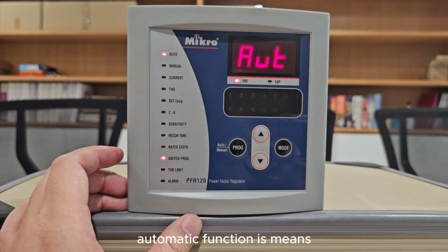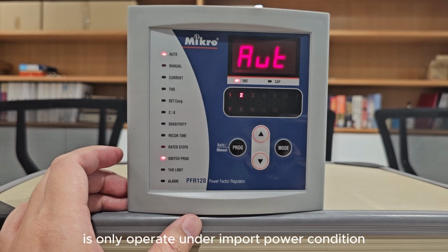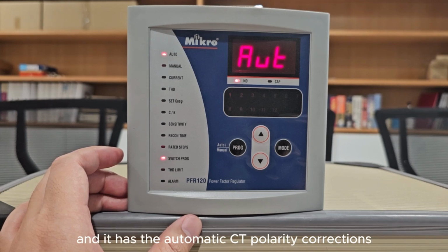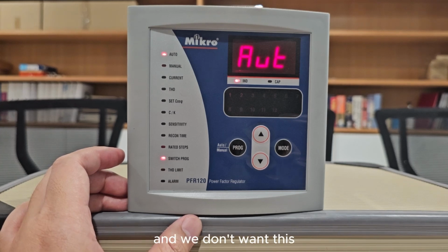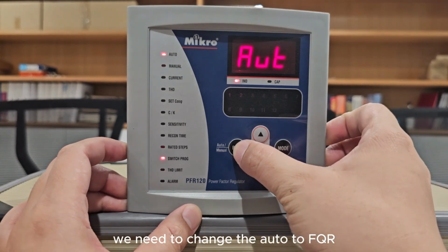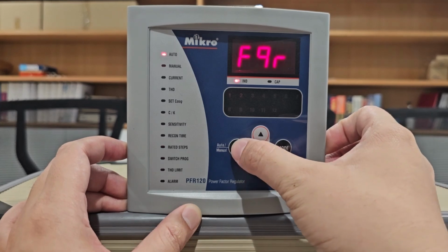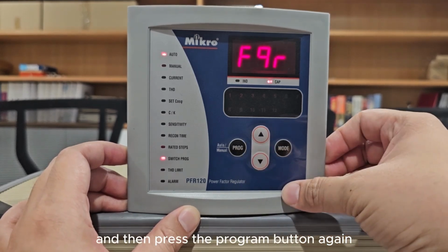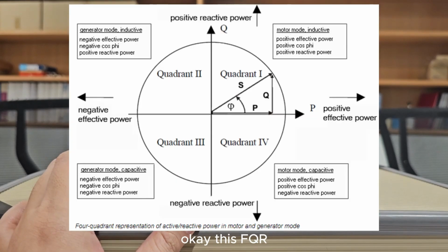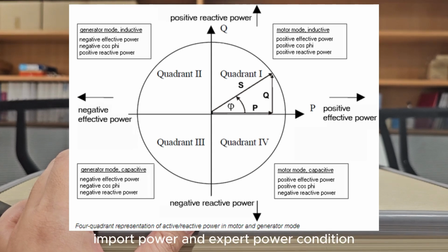Automatic function means it only operates under import power condition, and it has the automatic CT polarity corrections, and we don't want this. We need to change the auto to FQR and then press the program button again. Okay, this FQR switching program is similar to the automatic switching program, except that this switching program allows the power factor regulator to operate correctly under both import power and export power condition.